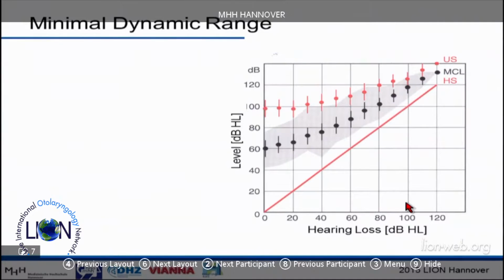What are the limitations of those bone conduction devices? If we plot the hearing loss against the level for the UCL, the threshold, and the MCL, we see that with a hearing loss of 0 dB there is an approximate dynamic range available in a normal hearing person between 100 decibel and 0 decibel. But this becomes narrower and narrower the more pronounced the hearing loss is.